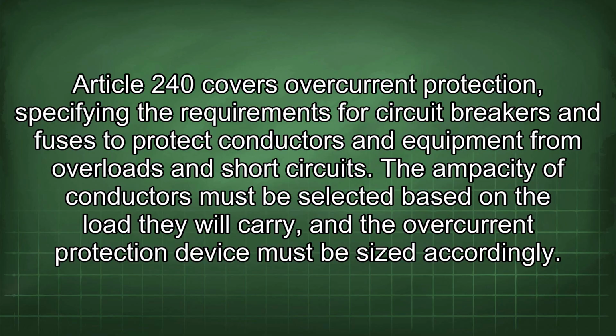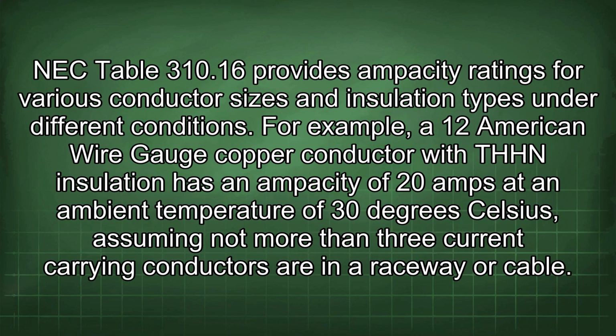The ampacity of conductors must be selected based on the load they will carry, and the overcurrent protection device must be sized accordingly. NEC Table 310.16 provides ampacity ratings for various conductor sizes and insulation types under different conditions. For example, a 12 American wire gauge copper conductor with THHN insulation has an ampacity of 20 amps at an ambient temperature of 30 degrees Celsius, assuming not more than 3 current carrying conductors are in a raceway or cable.